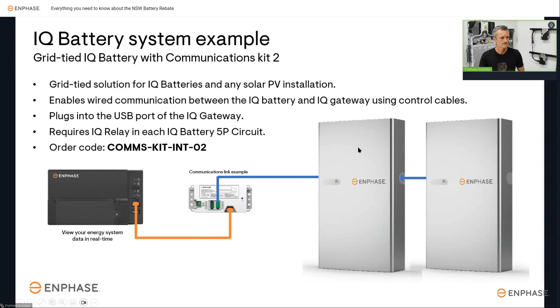Now let's put that into a system installation to understand it a bit more. Generally at Enphase you see a subboard built in with all those components already pre-built. We're seeing a lot of our wholesalers now supply pre-built subboards, like the example in the photo here, including the communications kit, the IQ relays, the switch gear, and the IQ gateway. It's an easy installation with that board, and you can buy those through the electrical wholesalers we supply into.